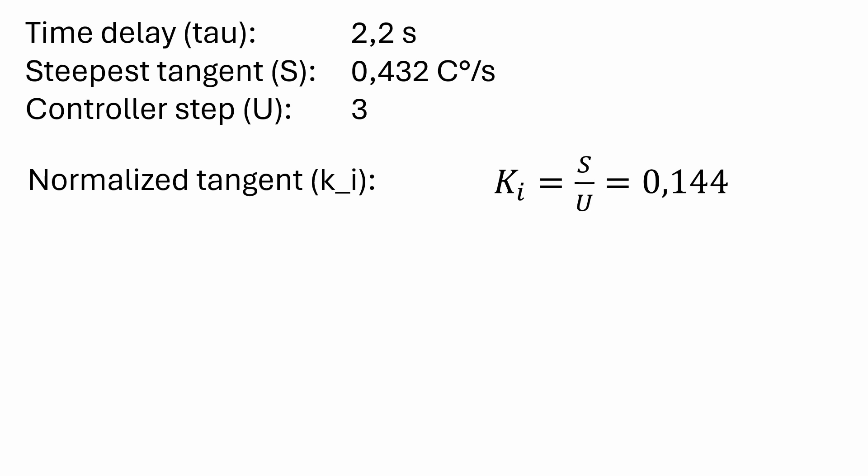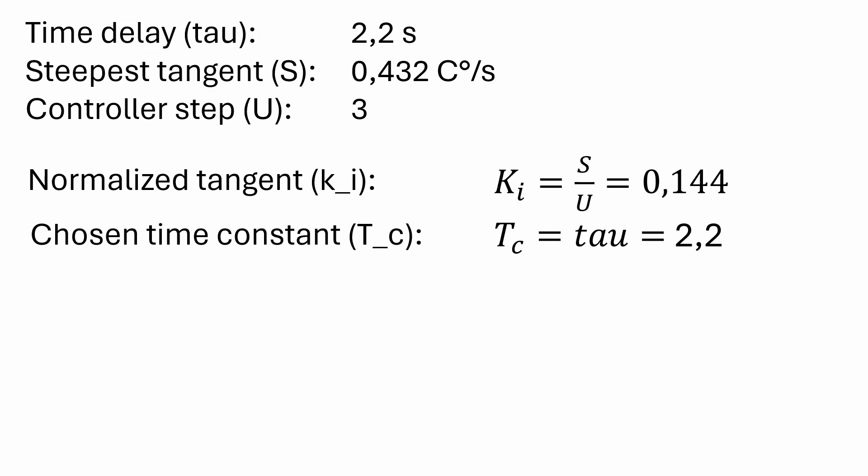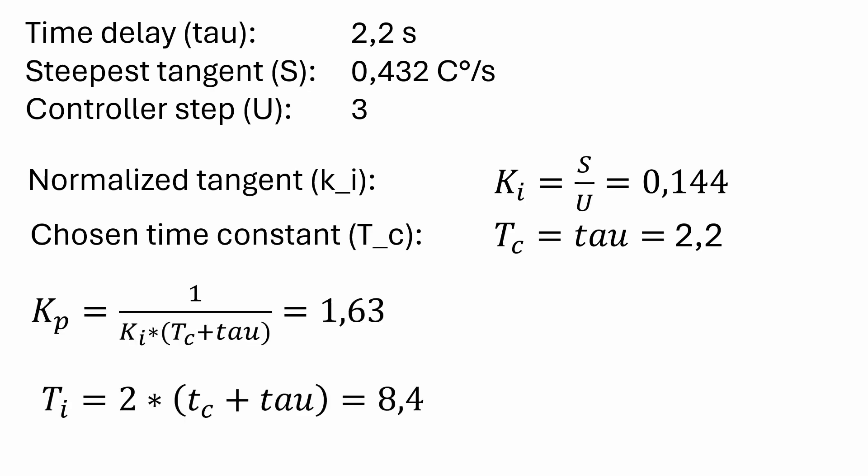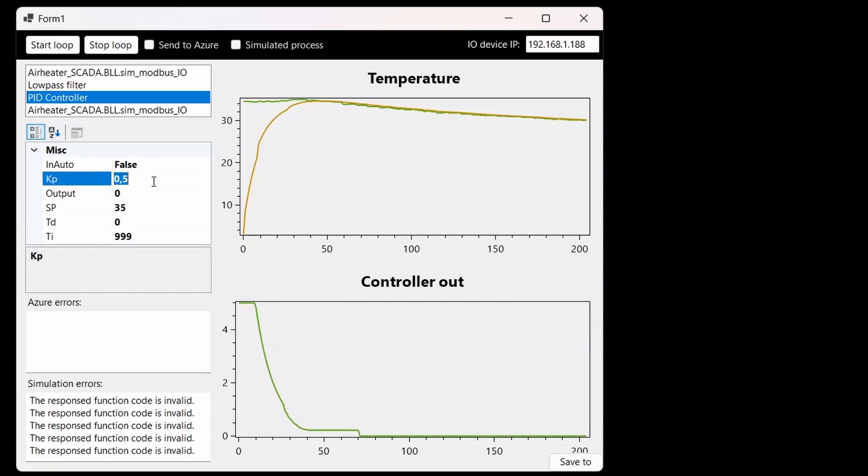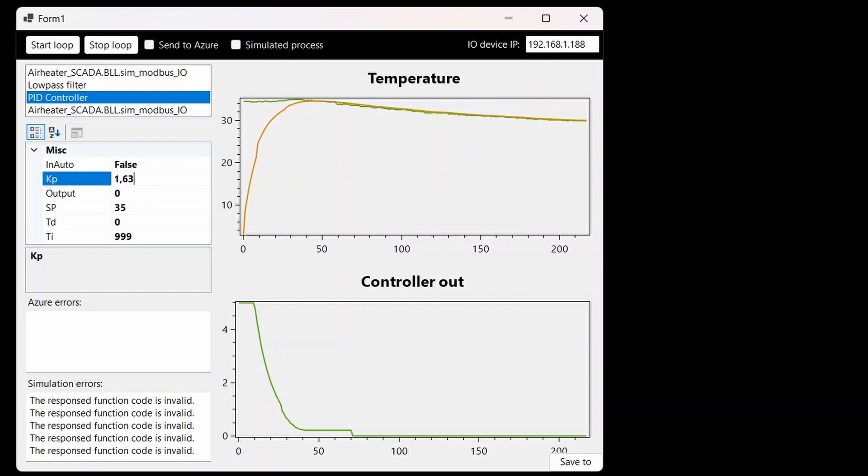Next we are going to decide the value Tc which is the time constant we want the final system with the controller to have. And the usual thing here is to set this equal to the time delay. So we set it to 2.2. Now we only need to apply the formulas for calculating the Kp the controller gain and the Ti the integral time. So we get these two values and these are the ones we are going to put into our PID controller.